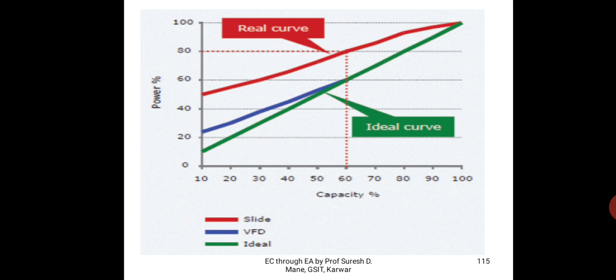Now coming to 10% loading, on the extreme left of the axis. For 10% loading also, in real life, you are consuming 50% of power. Is it acceptable? Even at 20%. At 30% capacity utilization, you are using 60% power. So that is why I told you should not go for part loading, you should go for full loading only. At 30% capacity, you are having 60% power consumption.